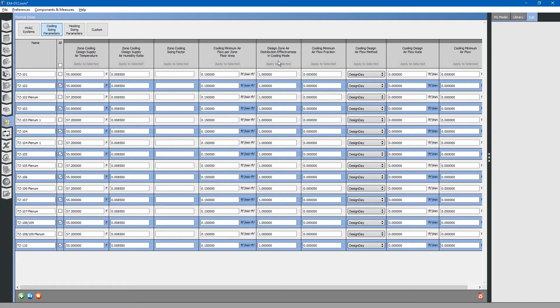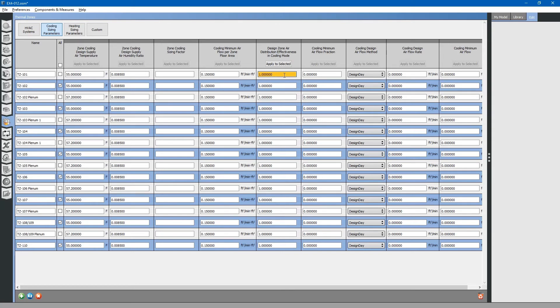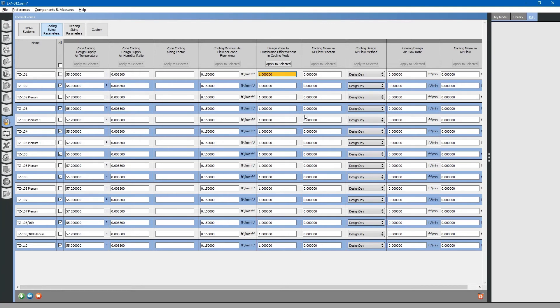Design zone air distribution effectiveness in cooling mode. This is based on the ASHRAE 62.1 ventilation rate procedure. We will just assume overhead air distribution for this. For cooling overhead air distribution effectiveness is 1 using the ventilation rate procedure.